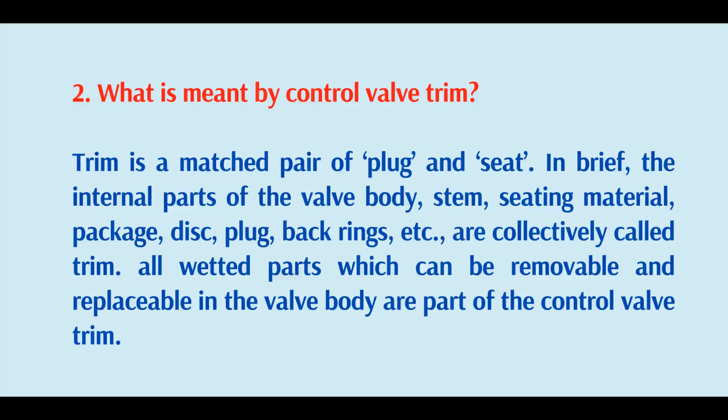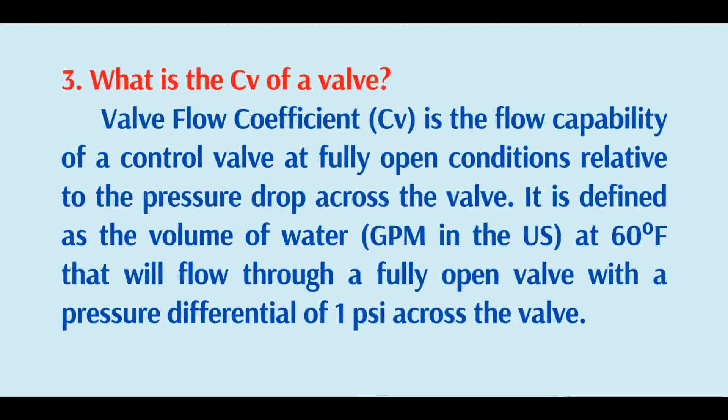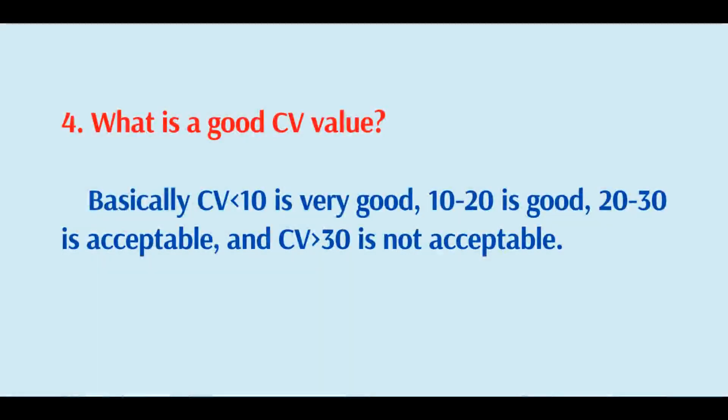What is Cv of a valve? Valve flow coefficient Cv is the flow capability of a control valve at fully open conditions relative to the pressure drop across the valve. It is defined as the volume of water in GPM at 60°F that will flow through a fully open valve with a pressure differential of 1 PSI across the valve.